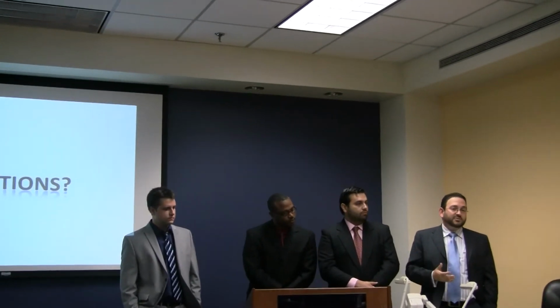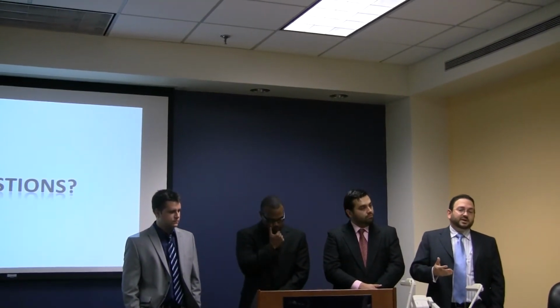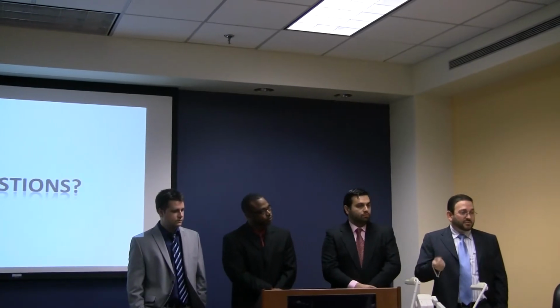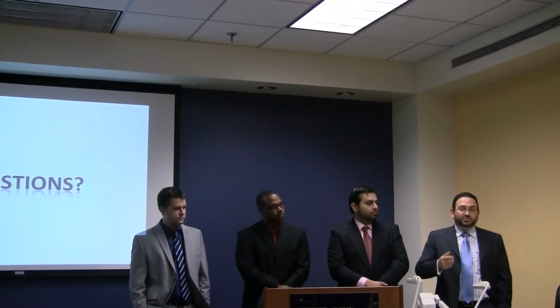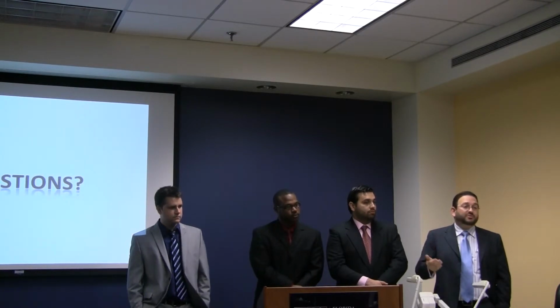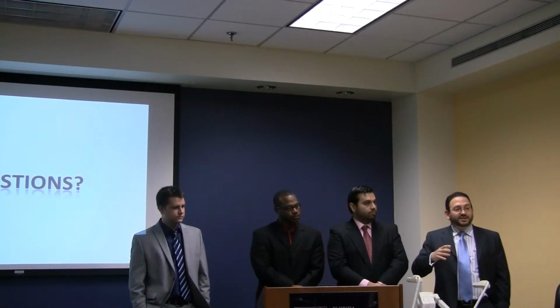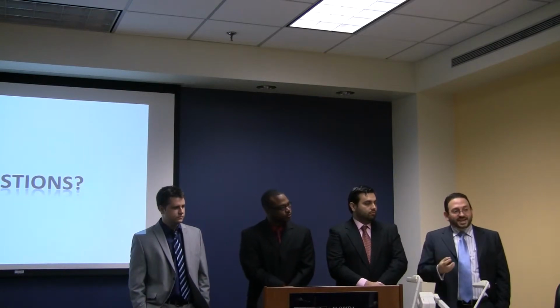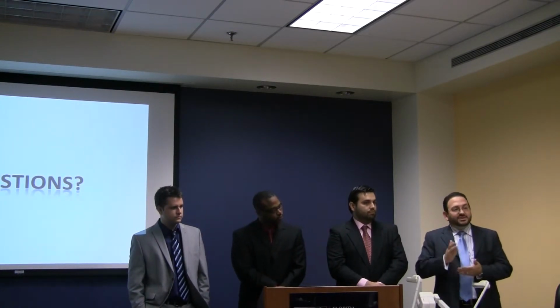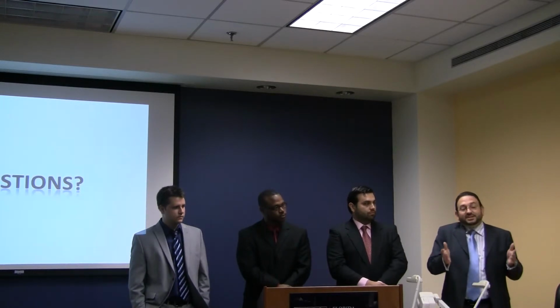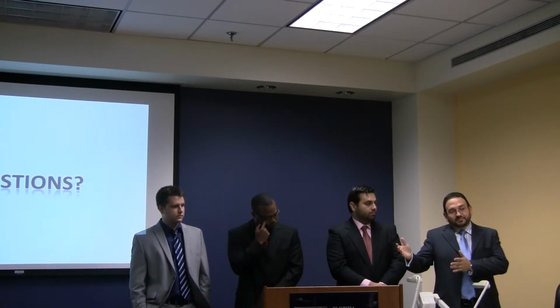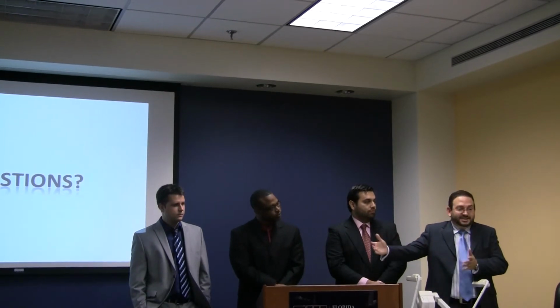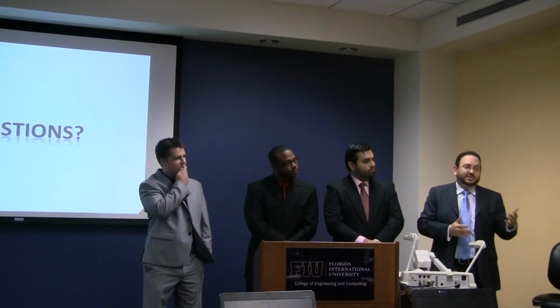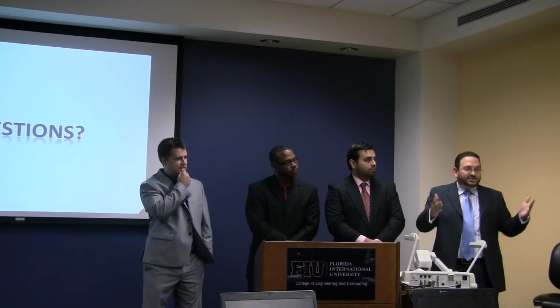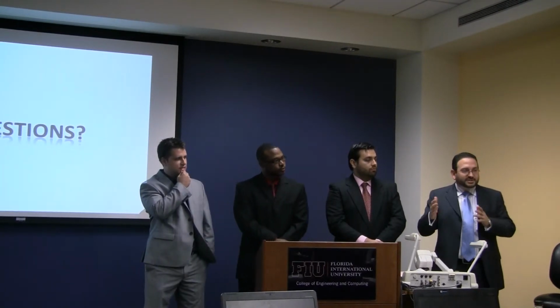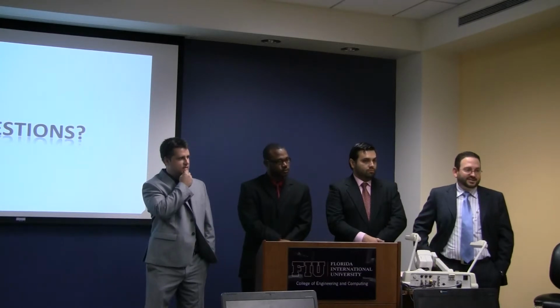We looked at Robur. Robur manufactures a 5-ton system. That system uses, I think it's ammonia instead of lithium bromide, and their vacuum is a lot less, so the temperature required will be a lot higher, somewhere north of 300 degrees. So part of our design and implementation is to find that balance: what can we build physically as a prototype, as opposed to what is the ideal. And the smaller we go, the higher that temperature is going to be. But again, the smaller we go, the less heat that we have to produce. So there is a break-even point in that design.